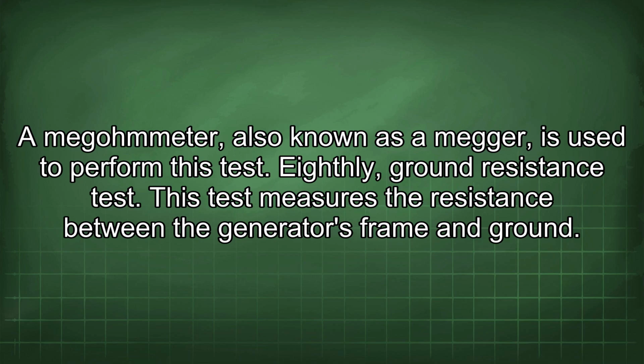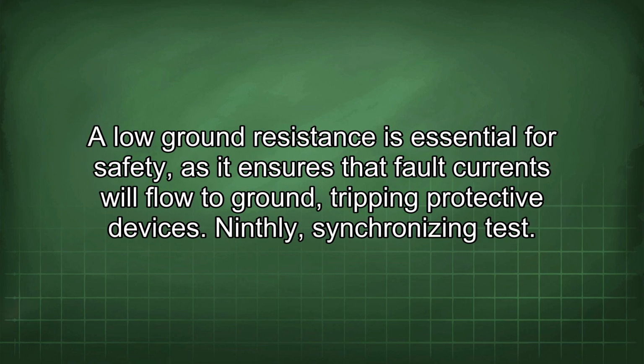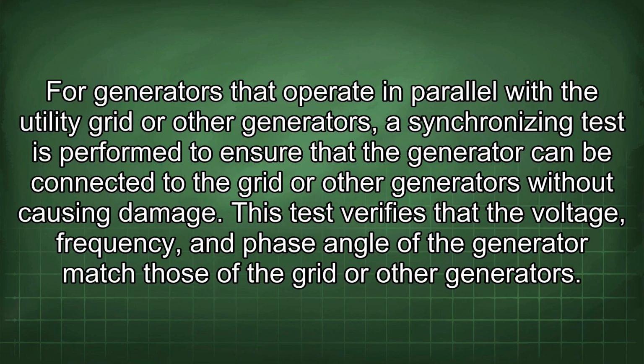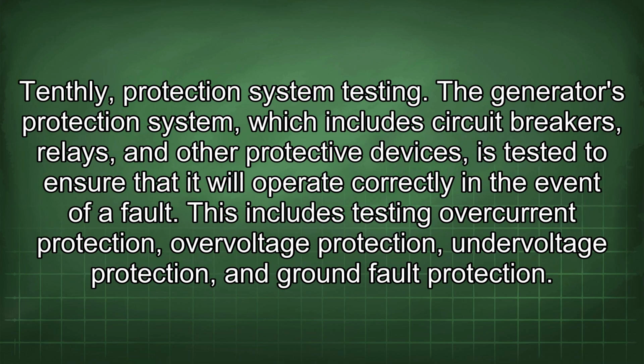Eighth, ground resistance test. This test measures the resistance between the generator's frame and ground. A low ground resistance is essential for safety, as it ensures that fault currents will flow to ground, tripping protective devices. Ninth, synchronizing test. For generators that operate in parallel with the utility grid or other generators, a synchronizing test is performed to ensure that the generator can be connected to the grid or other generators without causing damage. This test verifies that the voltage, frequency, and phase angle of the generator match those of the grid or other generators. Tenth, protection system testing. The generator's protection system, which includes circuit breakers, relays, and other protective devices, is tested to ensure that it will operate correctly in the event of a fault.